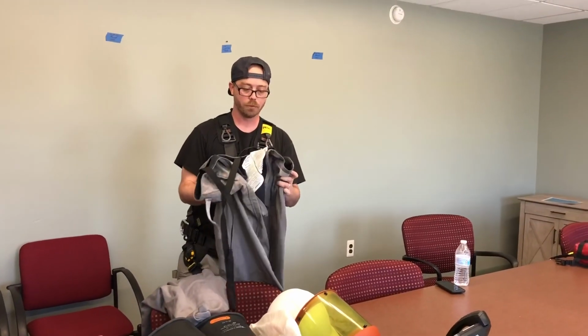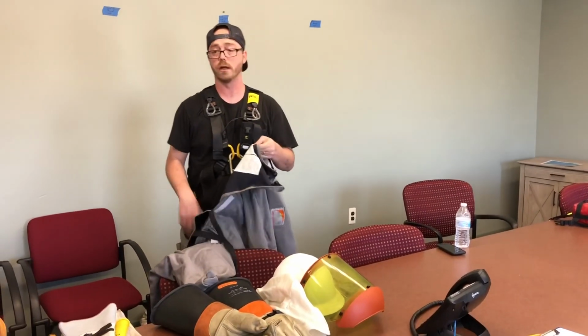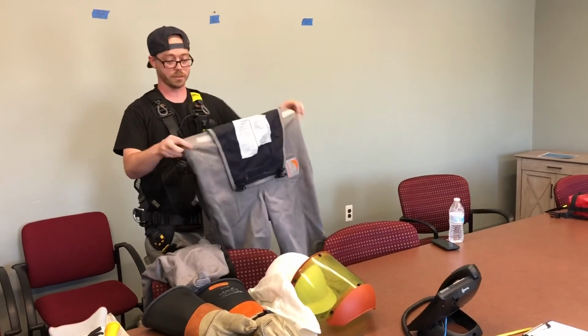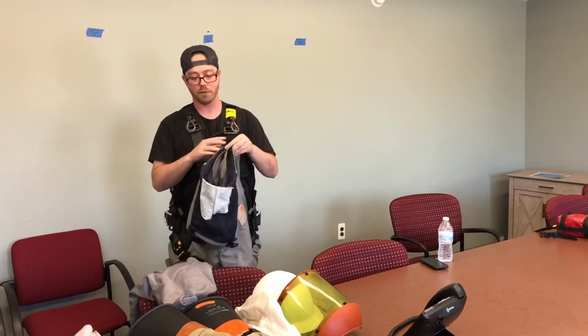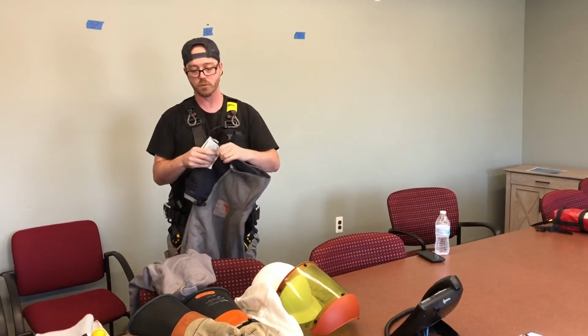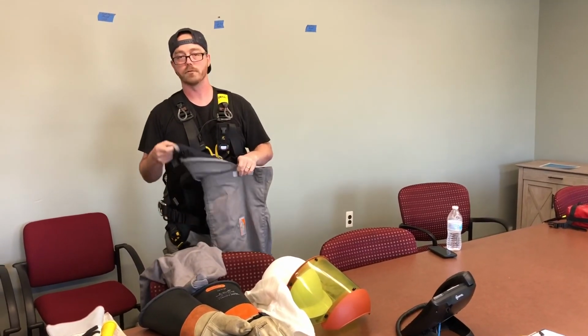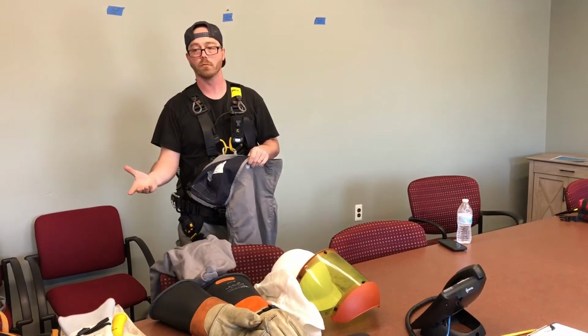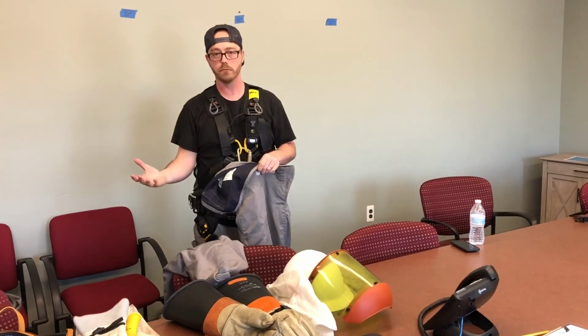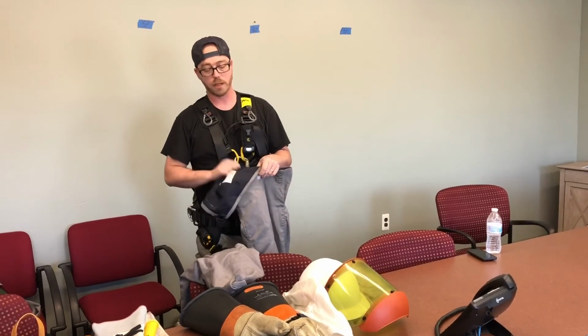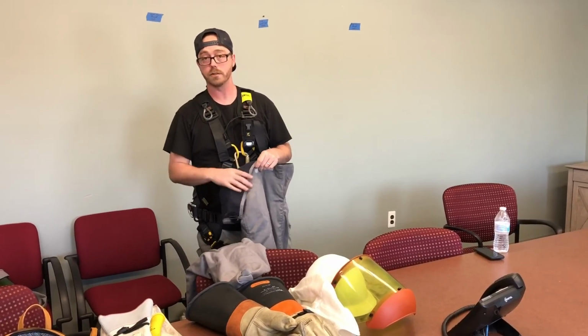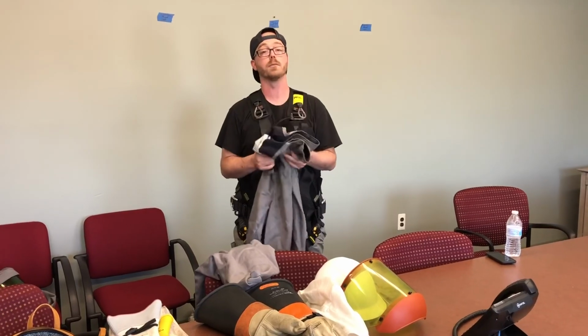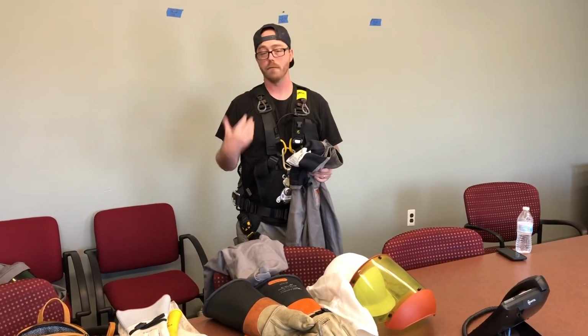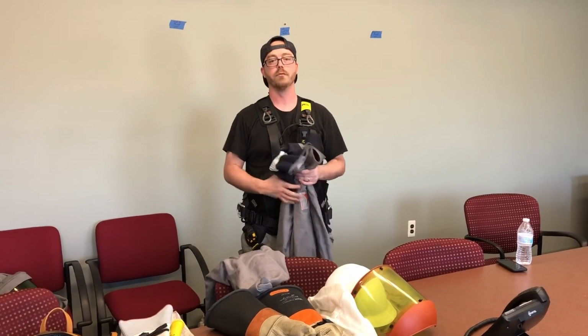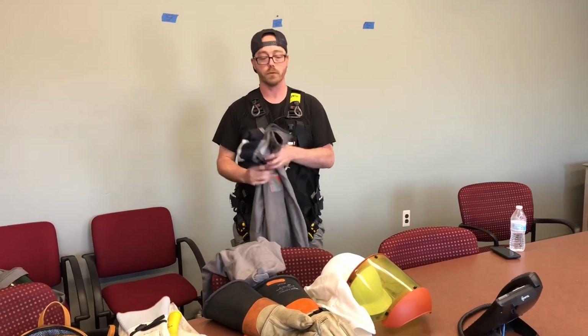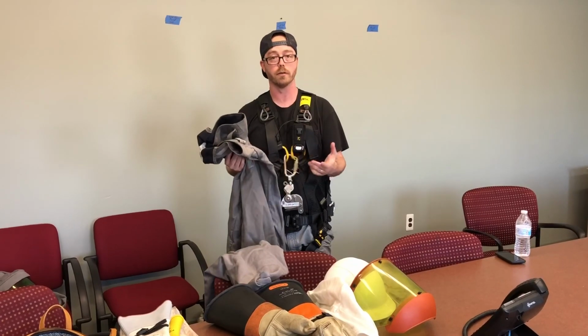This is there to essentially save you. It's fire resistant, and all these cabinets have arc flash rating studies done to say if something was to go wrong, this is the arc flash hazard for that cabinet. Depending on what that rating is, maybe it's dangerous enough that you need to put on a suit so that if there was a blast - and generally everything we work on is de-energized - but at some point you need to de-energize it, and so you may have to use this suit depending on the site and how it's configured.